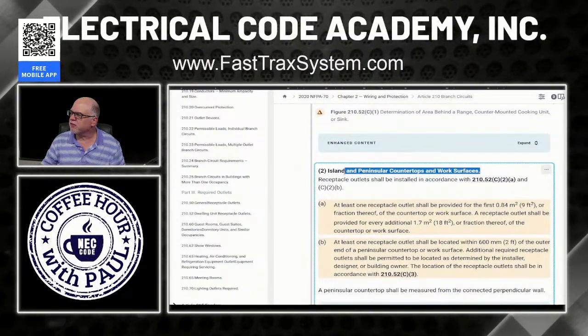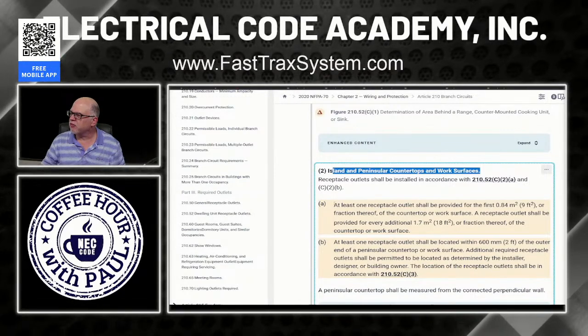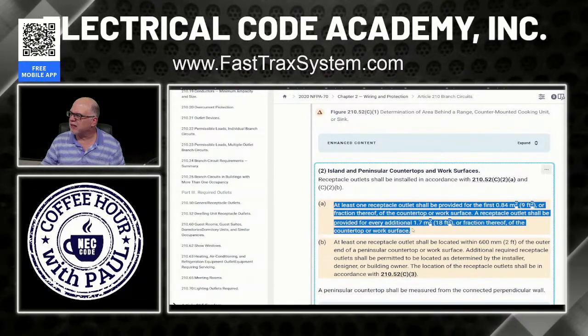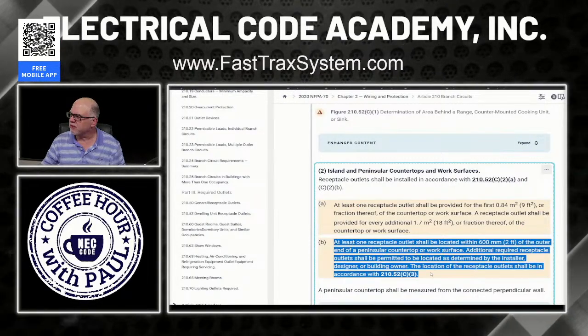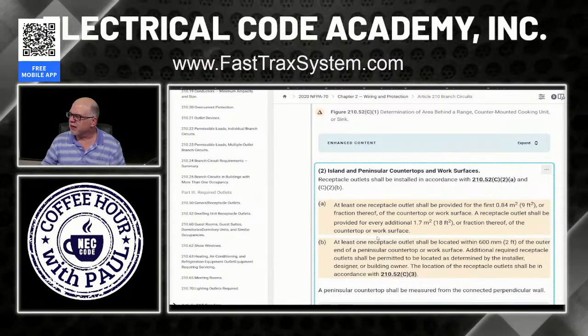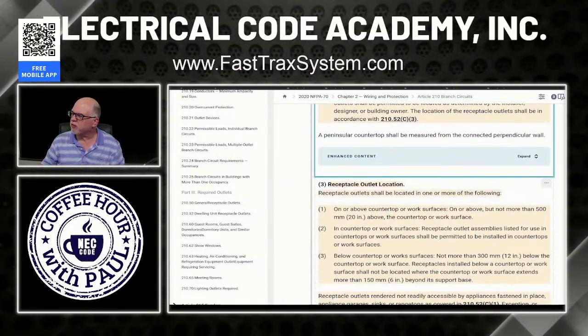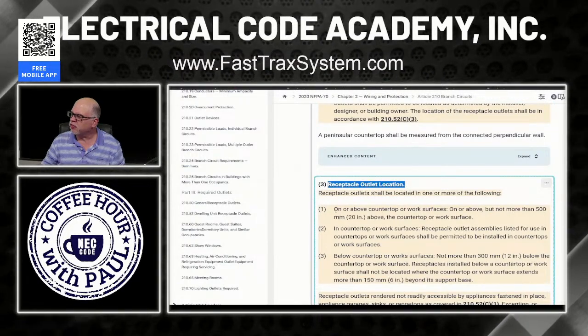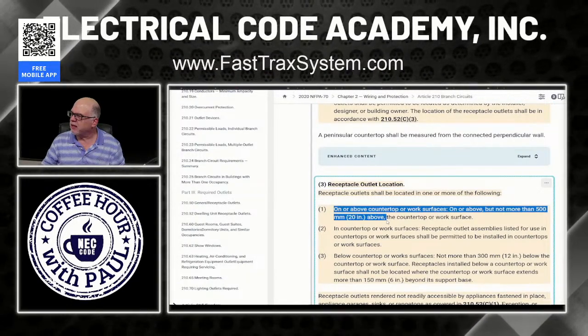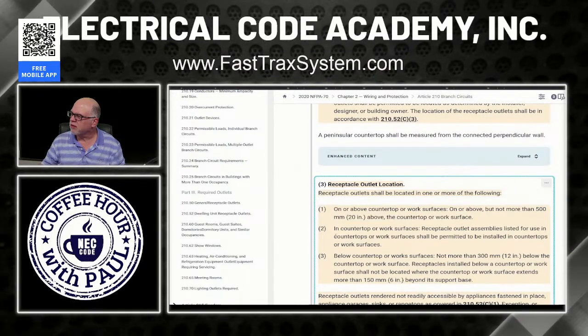Islands and peninsula countertops. Notice this is all grayed out. So this is where you get all your language. The first one applies to both islands and peninsulas. And then this one down here is specific to peninsulas, and gives you all that information. Now, the receptacle placements, this is right here. This is called receptacle outlet location. Again, you saw it before. It can be on or above the countertop, but not more than 20 inches.